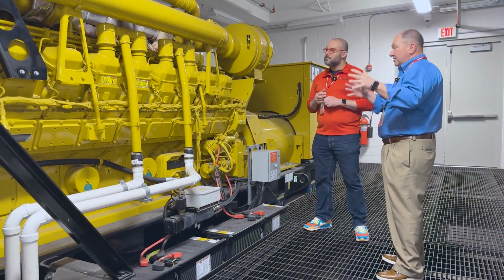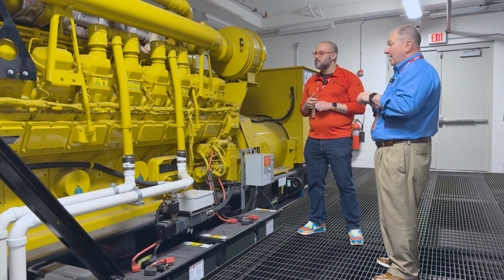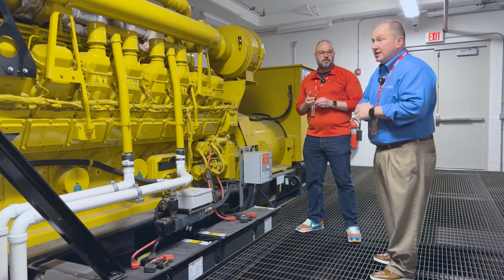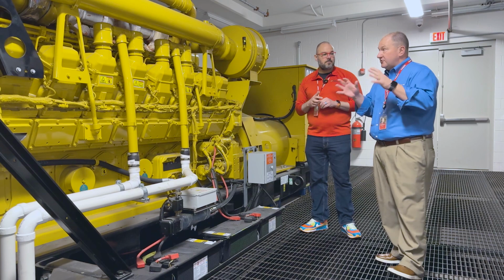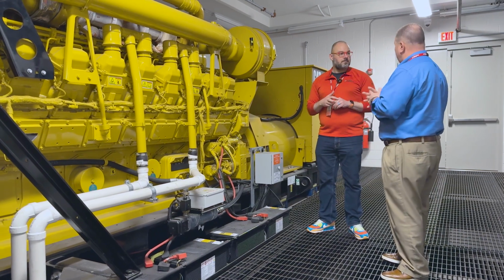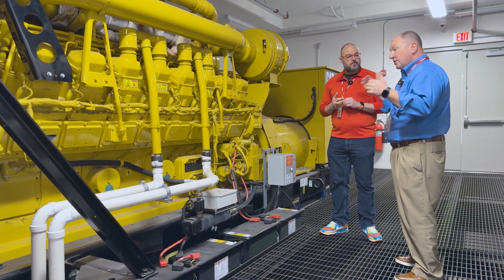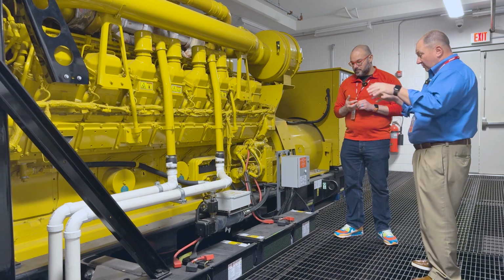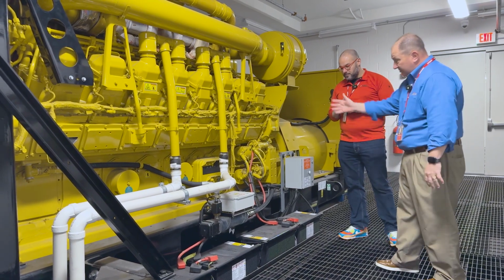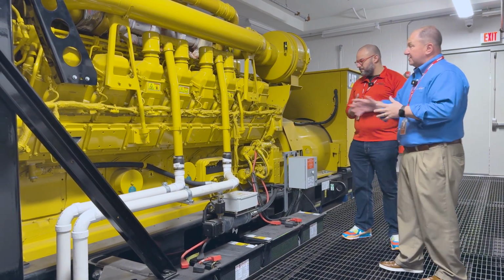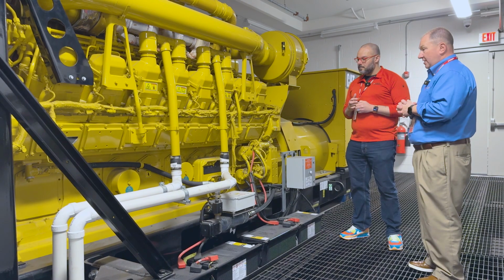So this system is 2 megawatts. We have 4 on site, which serves the space that we looked at. There's 2 here, so this is one of them, and we'll see the other one on the other side. But again, you talk about redundancy and resiliency - we have 2 sets of batteries, 2 starters, redundancy built into just this one single generator.